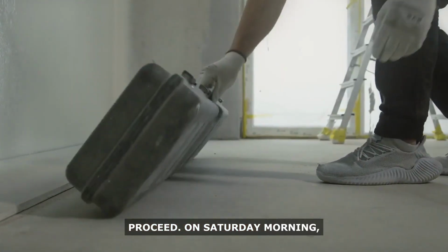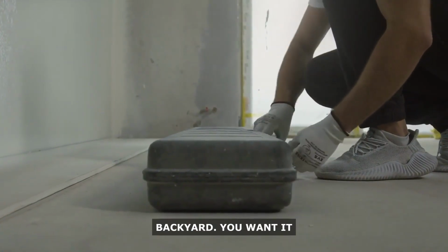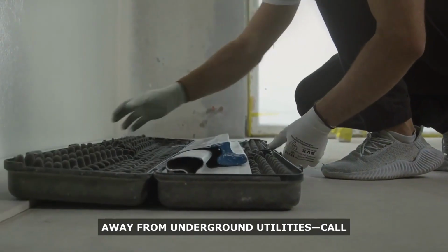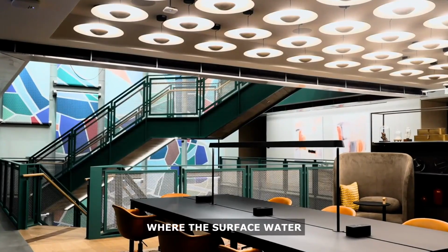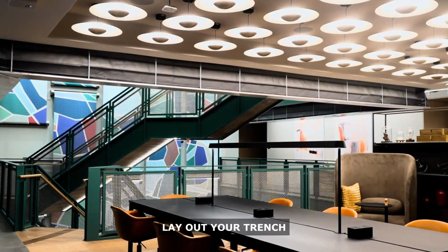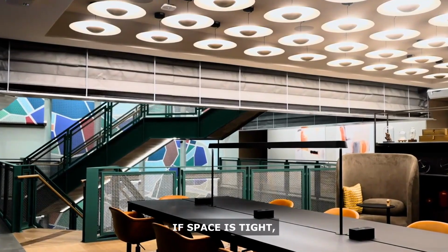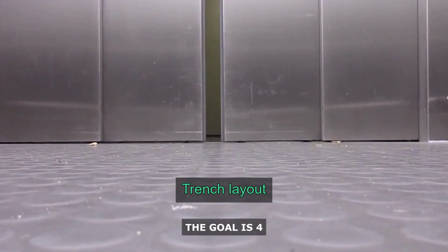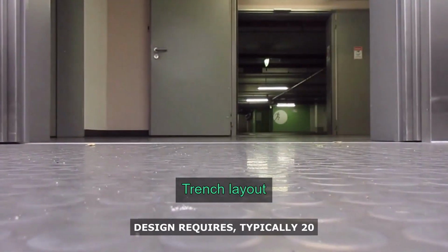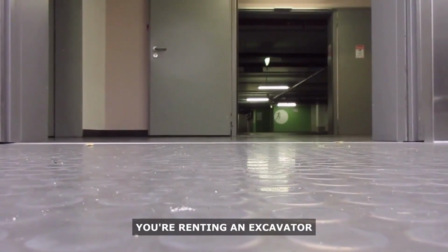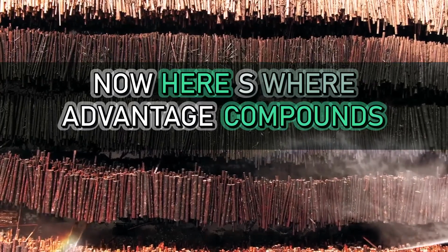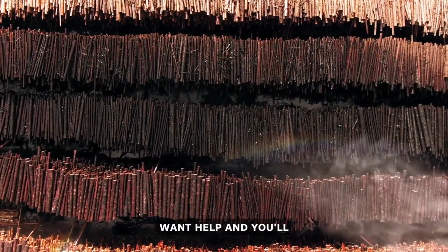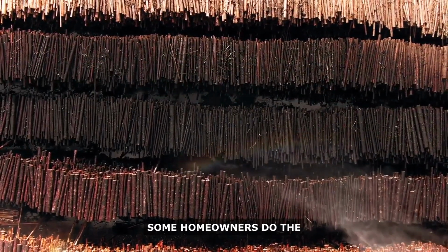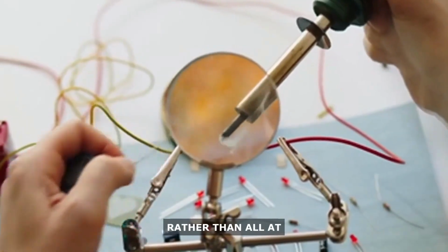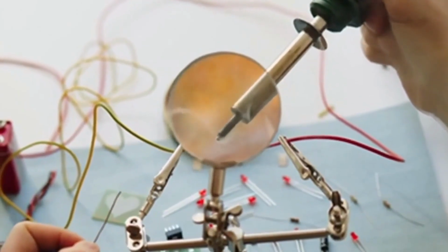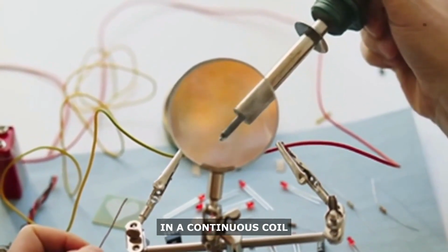The actual installation process is more straightforward than you might expect. Here's how a typical Saturday and Sunday build would proceed. On Saturday morning, you mark out your trench location in your backyard. You want it away from underground utilities. Call 811 to have them marked, and in a location where the surface water drains away naturally. You lay out your trench in a serpentine pattern if space is tight, or in gentle loops if you have room. The goal is 4 feet deep and as long as your coil design requires, typically 20 to 40 feet. If you're renting an excavator or hiring someone, this is their job. If you're doing it yourself with a shovel, you'll want help, and you'll want a clear Saturday. Some homeowners do the digging over several weekends rather than all at once.